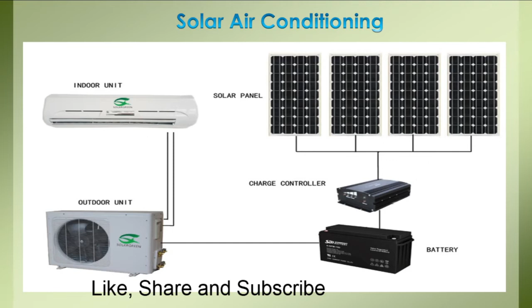This solar air conditioning works like a conventional air conditioner, which uses the utility grid supply. The two major differences are that the existing AC uses only the electricity grid and takes a higher wattage to run, while the solar AC is designed so that it takes a lower wattage. As we know, the wattage of 1 ton of AC might vary between 2000 watts and 2500 watts basically. But when we go for the solar air conditioning system, it consumes less wattage. For 1 ton, it consumes 1000 watts.